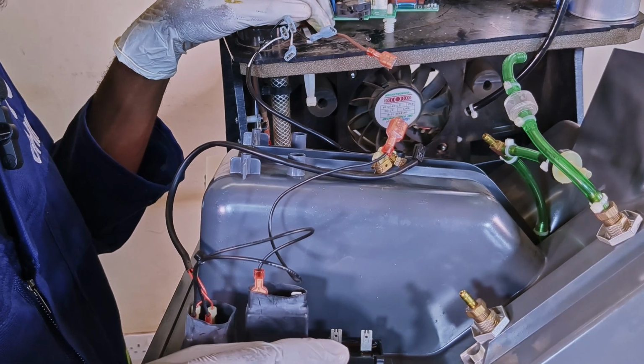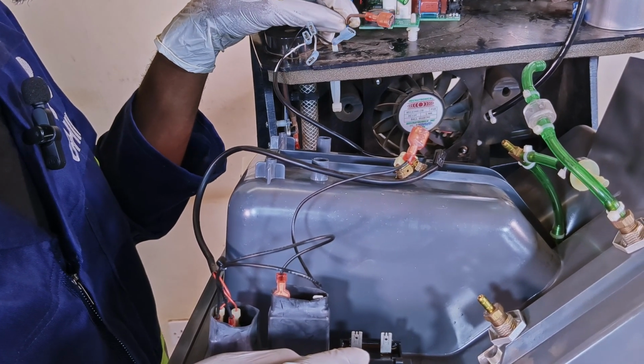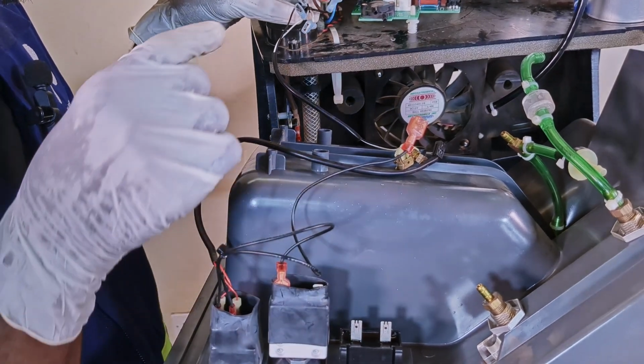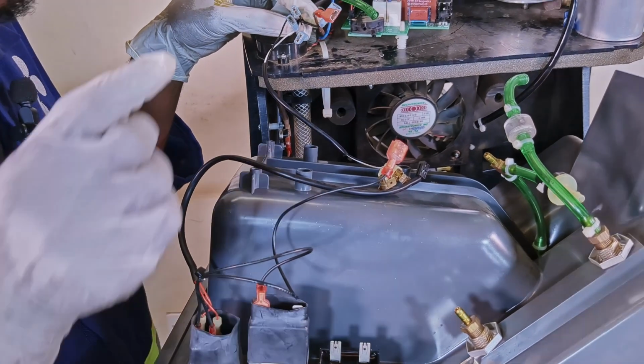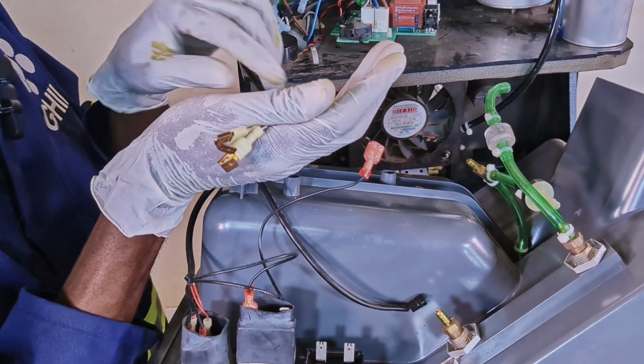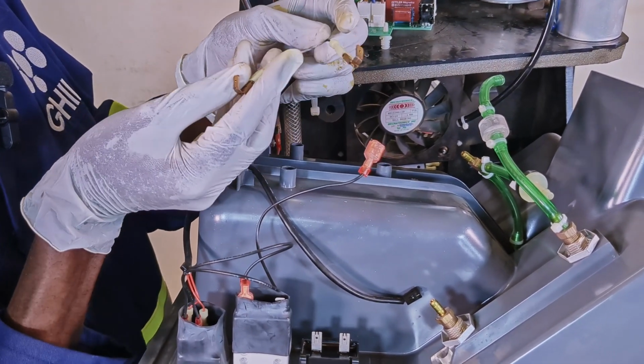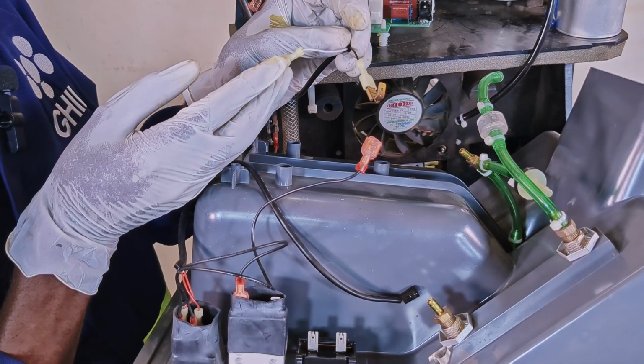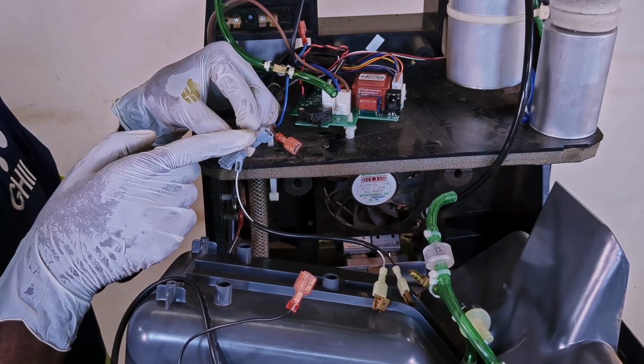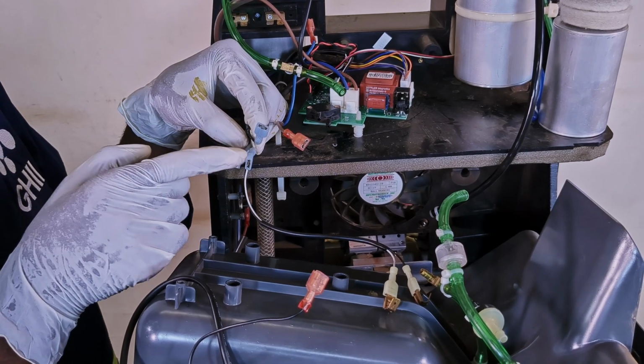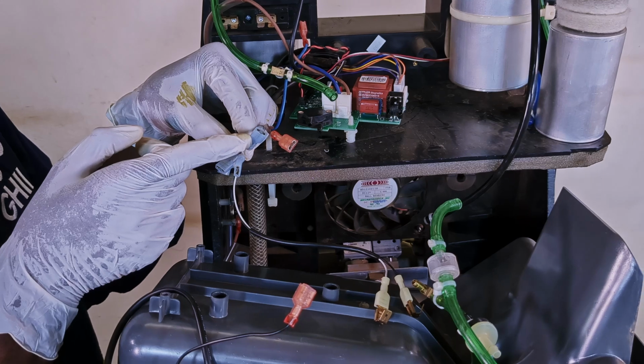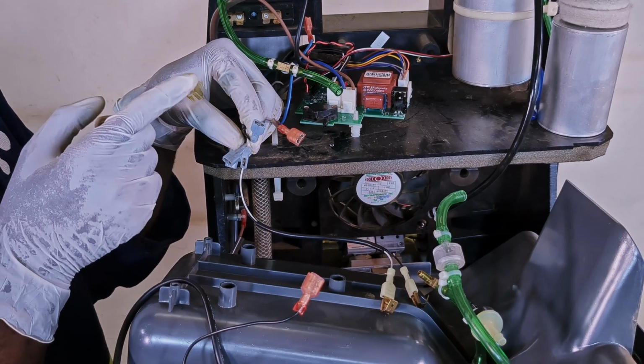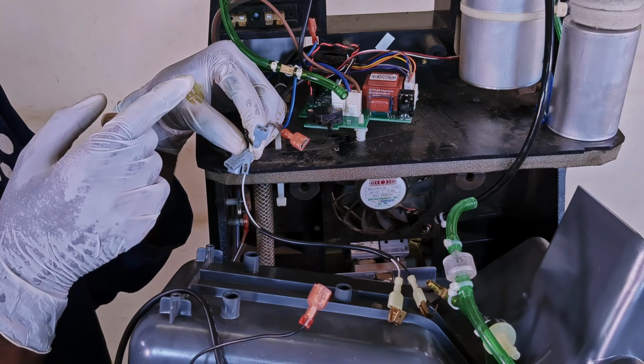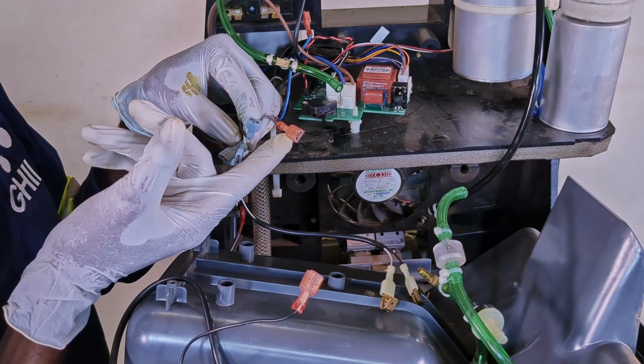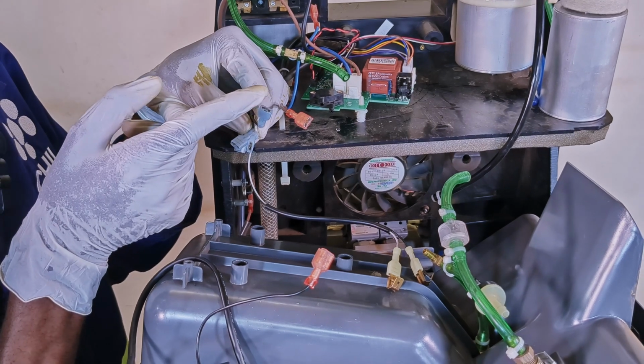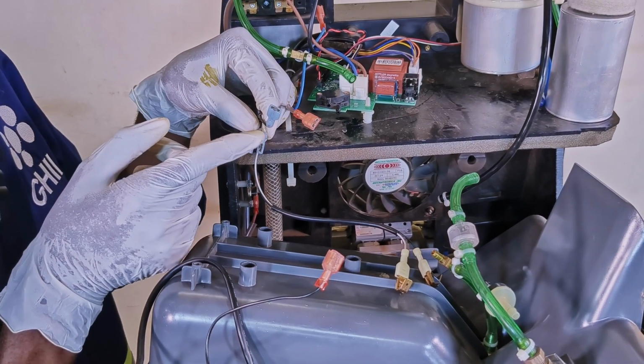Over here is the digital hour meter. The digital hour meter is connected in parallel with the live cable. The power cables for this digital hour meter are these two. The black one is for the live cable and the white one for the neutral cable. Over here you can see two cables, the white one being the neutral and the black one being the live. These cables are for the fan control board. The fan control board is connected in parallel with the live cable. This ensures that the board also receives 230 volts AC.